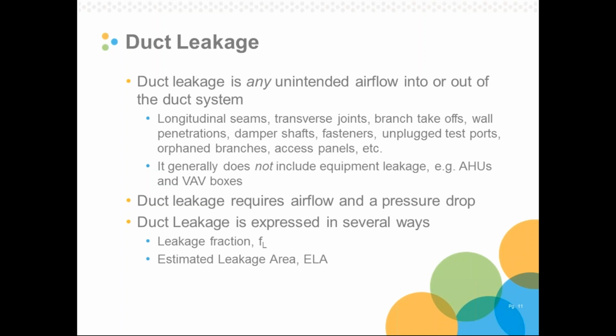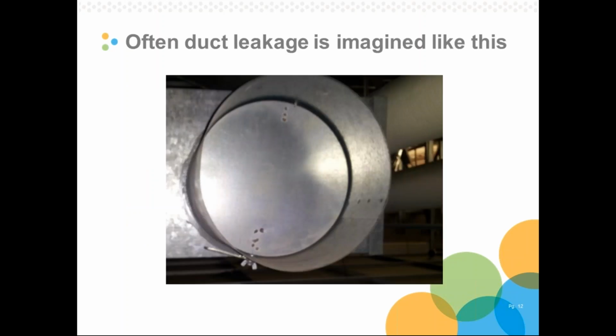In this project, and mostly in our final report, we really like talking about the leakage fraction. At the end of the day, what matters in an individual system is, at its nominal operating conditions, how much air does it leak. That's the air that's not available for ventilation, heating, cooling, and that's the air that's associated with energy penalties. So despite what I just said about all the many ways that air can leak out of duct systems, often people, and myself included, still imagine duct leakage to look like this.